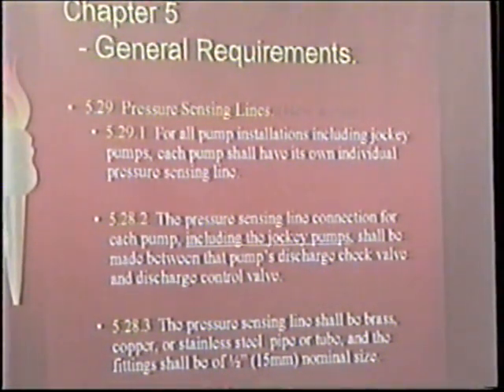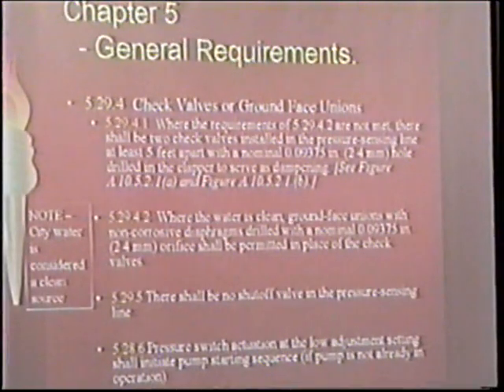Lately, the thing I've been seeing that I'm not sure I like is the gauges being mounted on a gauge valve, and that's also what they've tried to use for the test drain. So that valve is serving dual purpose. There's no way to isolate it if you have to change a gauge, or if you have to change the valve, because those valves do go bad. I think the idea of having a separate ball valve or a gate valve or whatever, and then the T with the gauge, and then the other valve or gauge, works better. But I didn't go back and verify all this word for word, but when I read through it, there's nothing new here. It's just the fact that it's up in the code. Yeah.